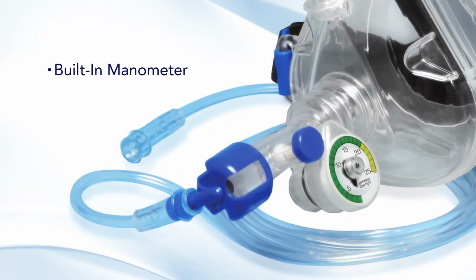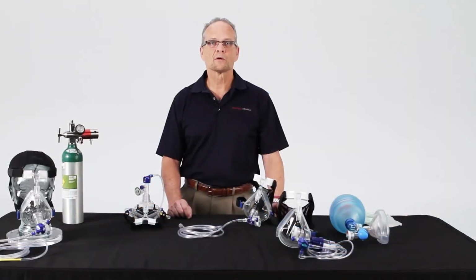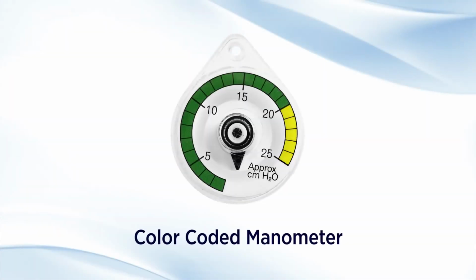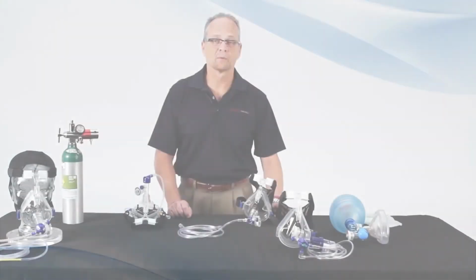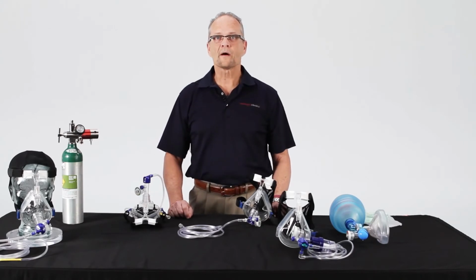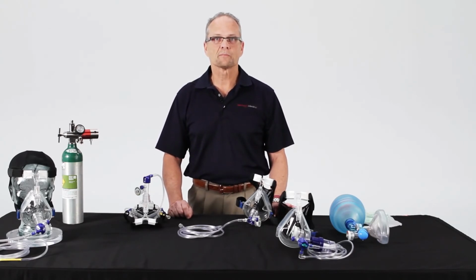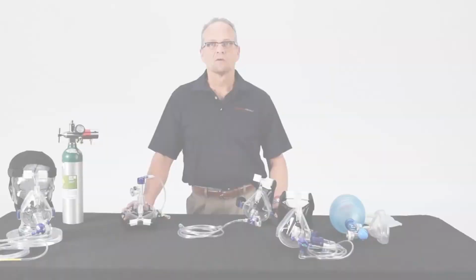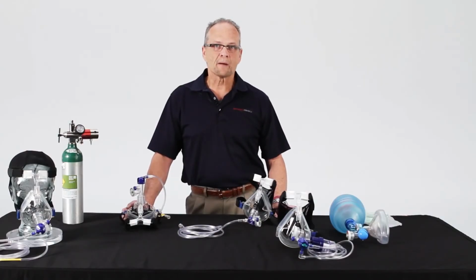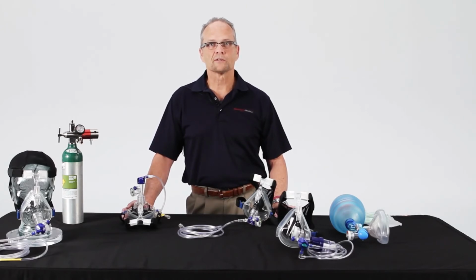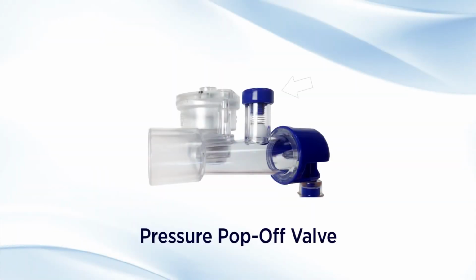Anytime a patient is on CPAP, a pressure manometer should be mandatory to accurately provide pressure and to be able to document what pressure the patient received, which could be critical from a legal standpoint. Without a manometer, how do you accurately titrate the pressure being provided to the patient? Well, the answer is simple. You can't. FlowSafe 2 is an open-circuit CPAP device, so anything that may block the end could cause an increase in pressure. The pressure pop-off valve will prevent the pressure from harming the patient.